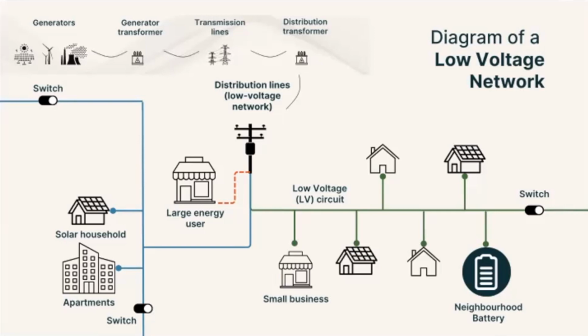Another thing that happens on these conductors is when you're exporting a lot of solar during the day, if it's not being used, it's actually pushing the voltage up. When the voltage gets too high, solar inverters sometimes trip, shut down, or begin derating. When the solar inverter is derating, it reduces the amount of solar power you're able to access if you have solar panels.